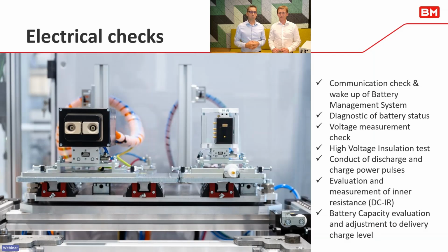The next test scenario is to conduct high power discharge and charging pulses to see the behavior and functionality of the battery. We measure these values at a highly accurate level to evaluate the respective DCIR, which is the inner resistance of the battery, to see if the high voltage part of the battery is working correctly in relation to the inner resistance of the cells, so that the system fulfills the lifetime requirements of the product. With those values, we can also evaluate the battery capacity, which is quite important for the functionality and lifetime of the battery. Depending on the required state of charge for delivery, we can charge or discharge to the certain level required of the battery.